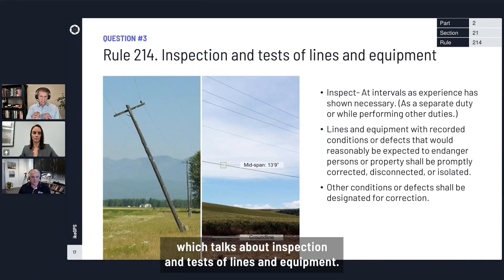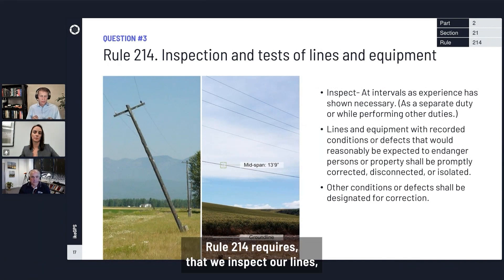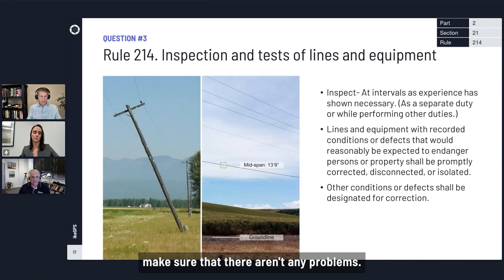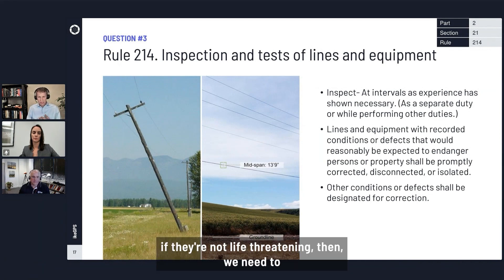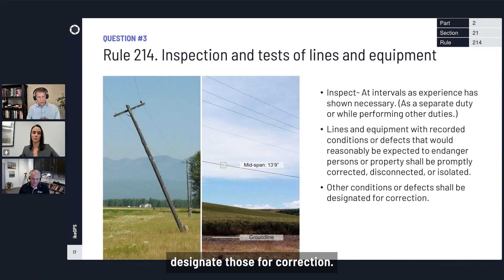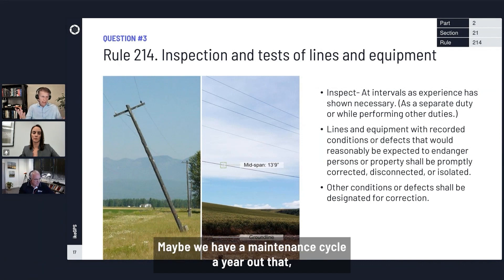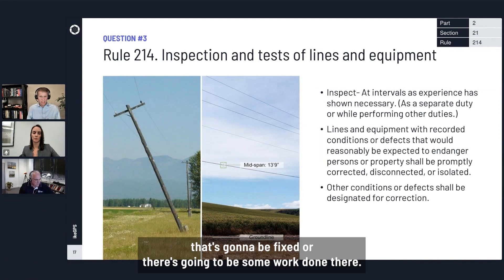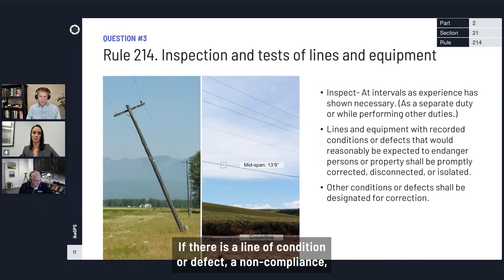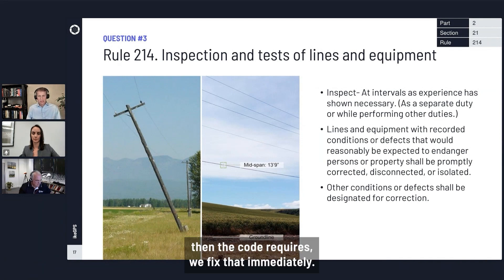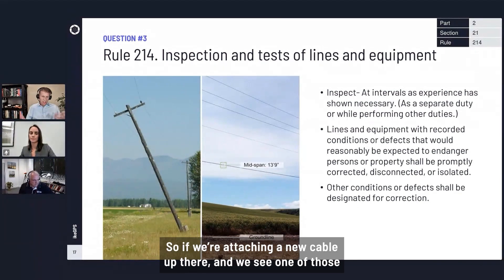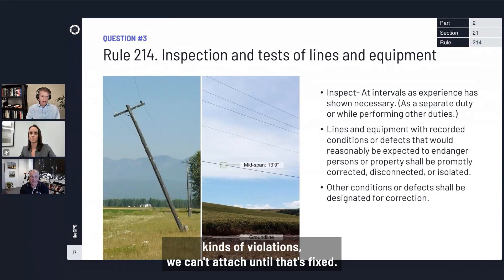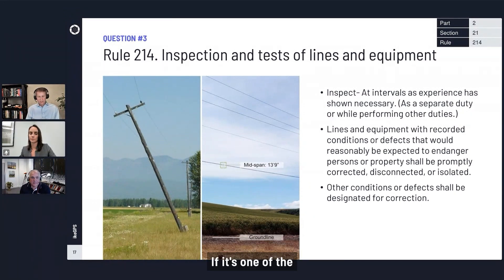The other rule that comes into this a lot is Rule 214, which talks about inspection and tests of lines and equipment. Rule 214 requires we inspect our lines and make sure there aren't any problems. If there are problems, Rule 214 a4 says if they're not life-threatening, we need to designate those for correction — maybe we have a maintenance cycle a year out. But if there is a condition or defect that could endanger life or property, the code requires we fix that immediately. So if we're attaching a new cable and we see one of those violations, we can't attach until that's fixed.